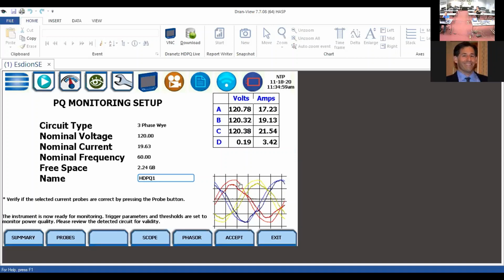The other thing you have, from a graphical perspective, is your built-in scope. Ross showed you an example of lifetime scope where you get this oscilloscope type display. One of the most common things we see, particularly relating to CTs or current probes, is what we call reverse polarity. It shows up easily on this scope mode — here's my current for A, B, and C. If I was inverted, polarity inverted on the CT, then my current would actually be 180 degrees out.